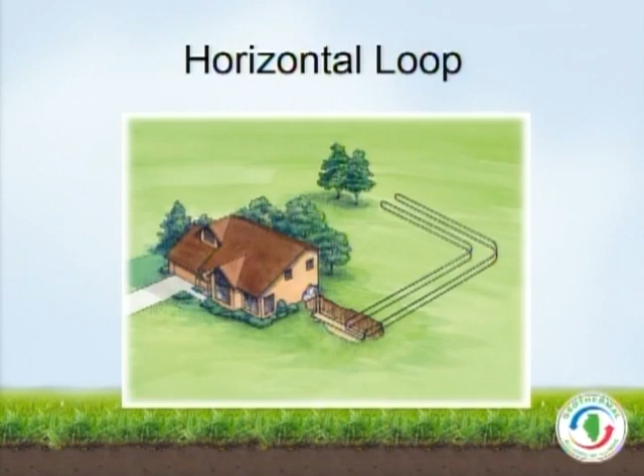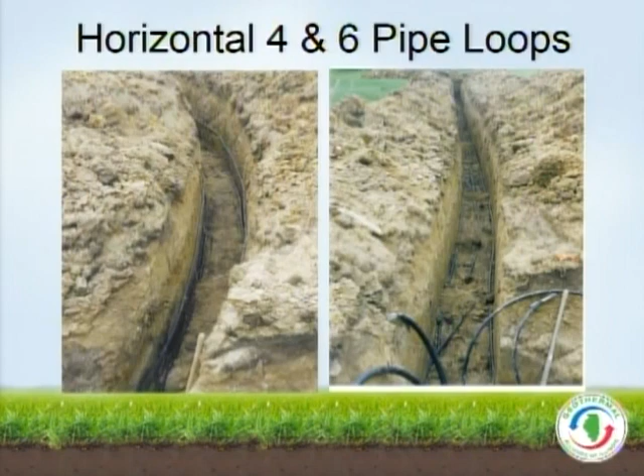Horizontal loops are common if you live out in the country or you're a farmer with plenty of property. This is what it looks like in application, slightly different but the same idea. You're typically digging a 5 or 6 foot trench and installing the loops in there, same as a vertical loop, only sideways and just under the ground. They work perfectly fine, but you need more loop in the ground with a horizontal than with a vertical. Personally, when I talk to people putting geothermal in, I say I like vertical loop fields. It costs a little more money, but you never hear of anybody digging up a vertical loop field. You do hear about digging up horizontal loop fields once in a while, and that makes for a very bad, expensive day. So for my money, just go ahead and do the vertical and you're done with it.